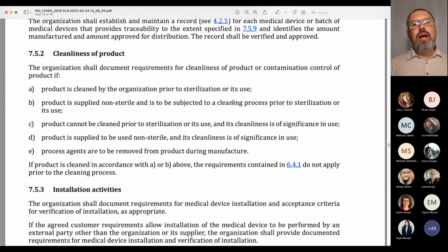And one of the elements of a cleaning validation is the ability to establish a baseline bioburden, meaning here is all of the bioburden that our manufacturing process introduces to the product prior to cleaning. Give it a number. Over the course of our manufacturing process, we put 100 worth of bioburden on this device, and we're going to show through our cleaning validation that our cleaning process reduces that bioburden from 100 to 0 or 100 to 20. And then after we send it to sterilization, sterilization is going to kill the remaining 20, and then it's going to go on, right?